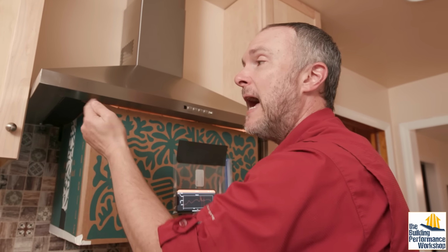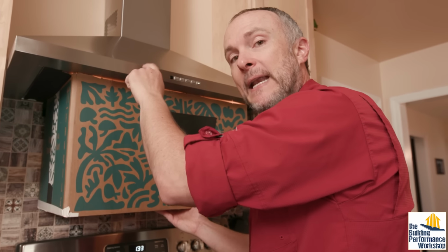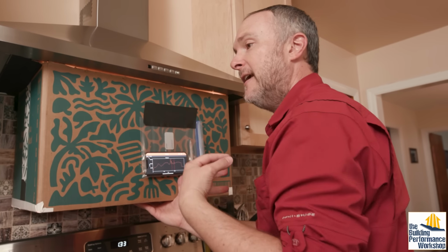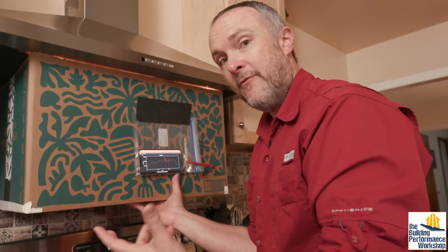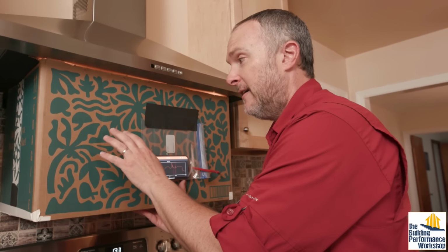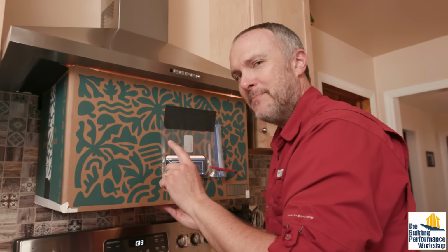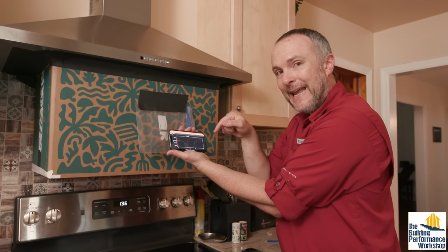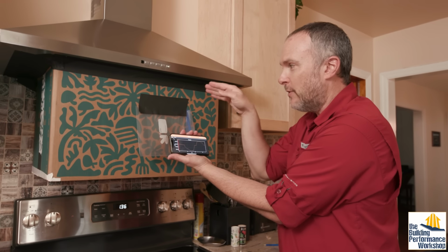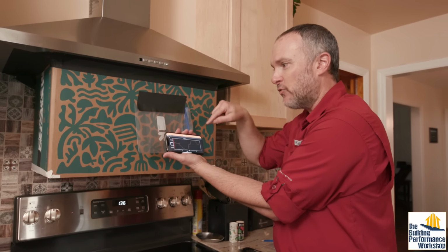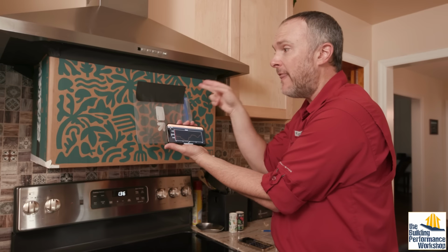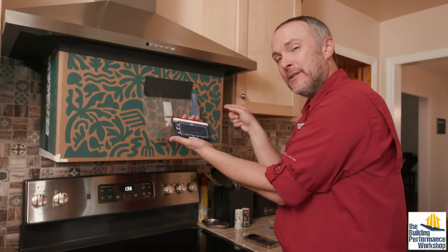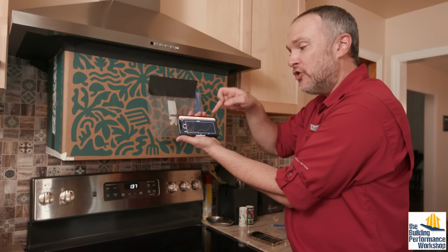It's okay. I'm not trying to measure how many CFM this fan moves in real life. I'm trying to use the fan as something to do a job for me, which is to just depressurize the whole house, but also to depressurize this box specifically so that we can get a number off of it. I took the phone back out of here because the two things we're doing is we want to measure the pressure inside the box while the fan is running, and also what that fan at that known pressure, which we're going to convert into a CFM for the fan, is doing to the house.